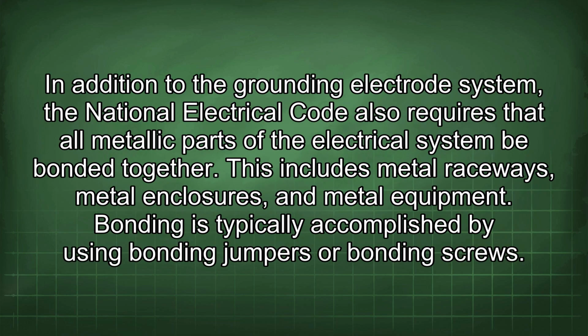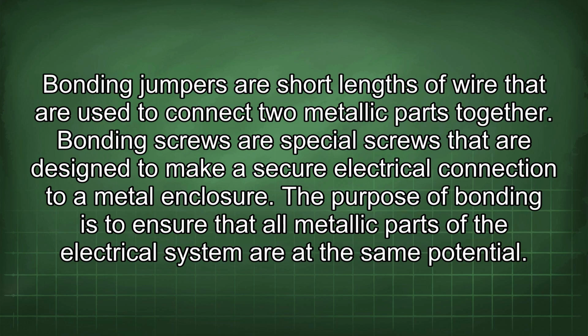In addition to the grounding electrode system, the National Electrical Code also requires that all metallic parts of the electrical system be bonded together. This includes metal raceways, metal enclosures, and metal equipment. Bonding is typically accomplished by using bonding jumpers or bonding screws. Bonding jumpers are short lengths of wire that are used to connect two metallic parts together. Bonding screws are special screws that are designed to make a secure electrical connection to a metal enclosure.